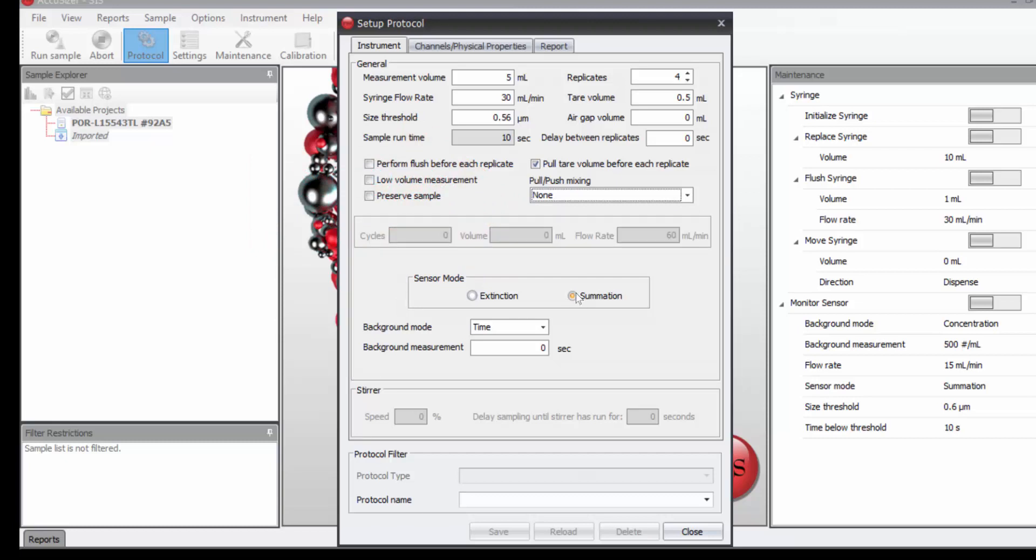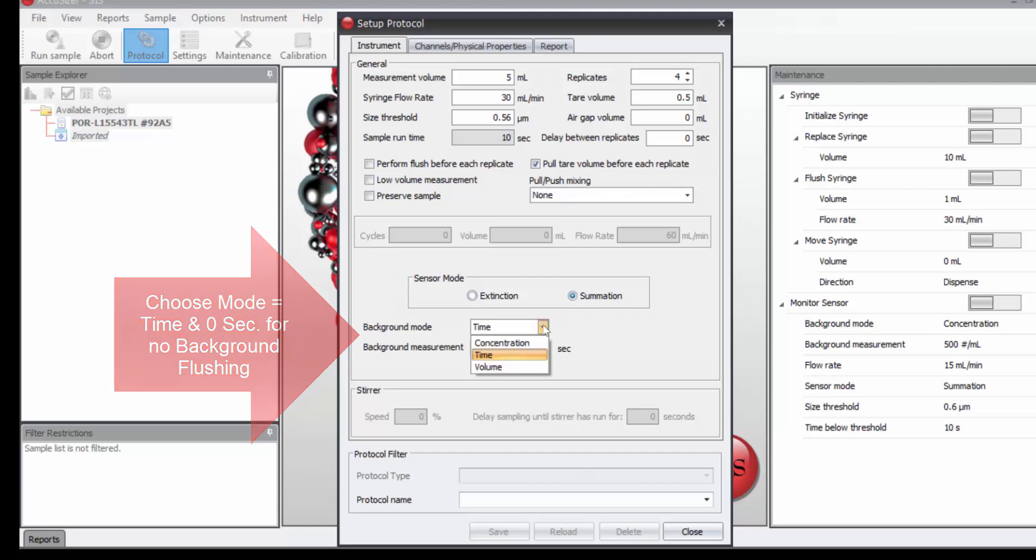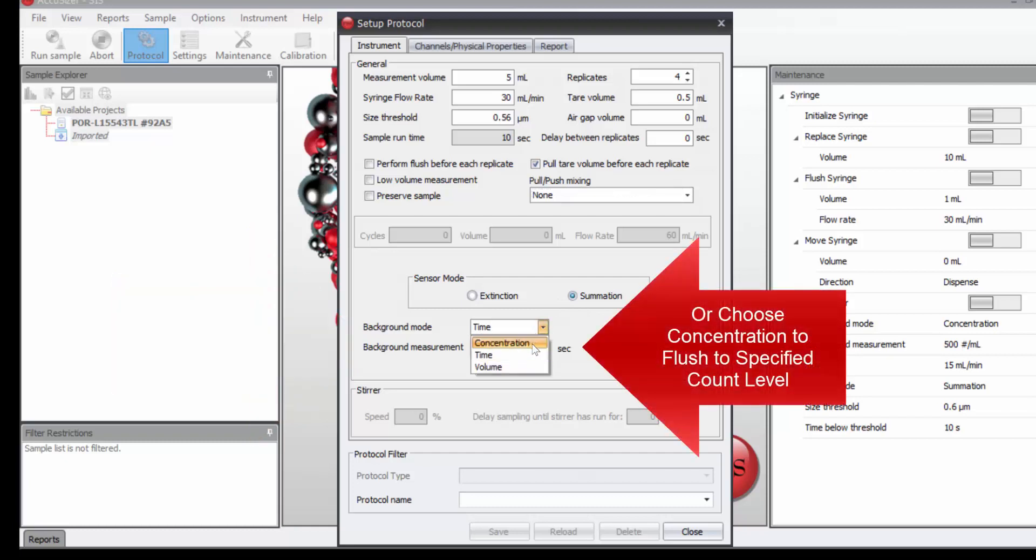I'm working in summation so that we can measure down to 0.5 microns. I'm not going to do an automatic background test, so I just choose background time and 0 seconds.